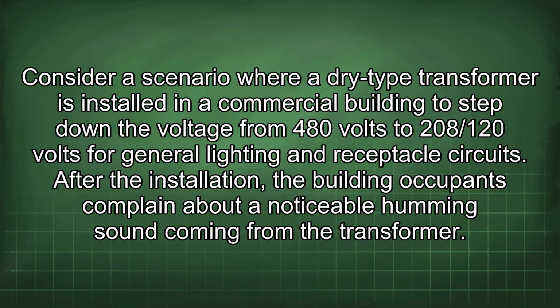Consider a scenario where a dry-type transformer is installed in a commercial building to step down the voltage from 480 volts to 208/120 volts for general lighting and receptacle circuits. After the installation, the building occupants complain about a noticeable humming sound coming from the transformer.